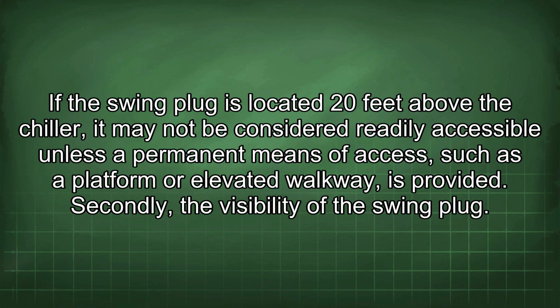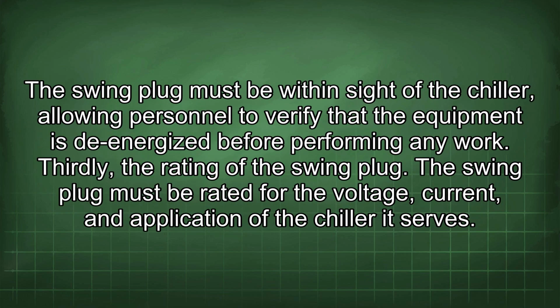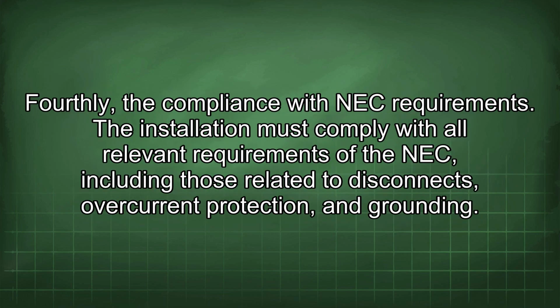Secondly, the visibility of the swing plug. The swing plug must be within sight of the chiller, allowing personnel to verify that the equipment is de-energized before performing any work. Thirdly, the rating of the swing plug. The swing plug must be rated for the voltage, current, and application of the chiller it serves. Fourthly, compliance with NEC requirements. The installation must comply with all relevant requirements of the NEC, including those related to disconnects, overcurrent protection, and grounding.